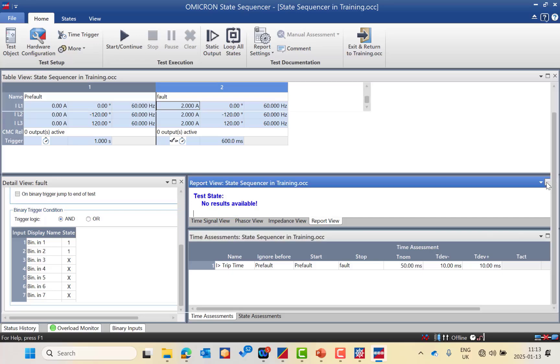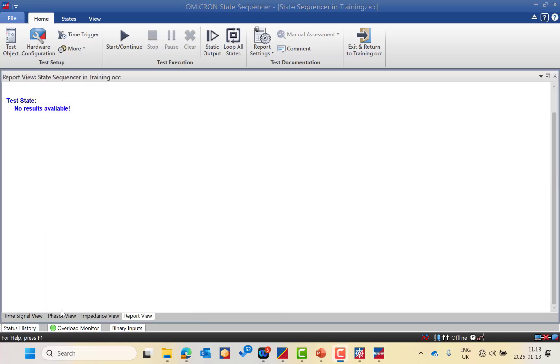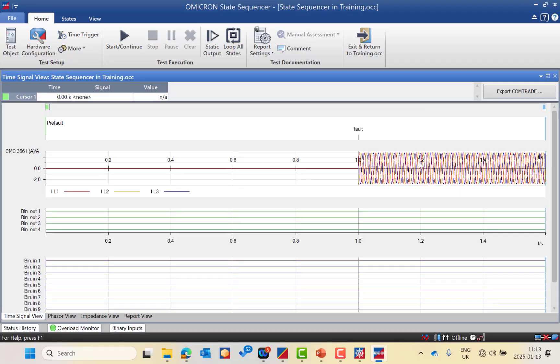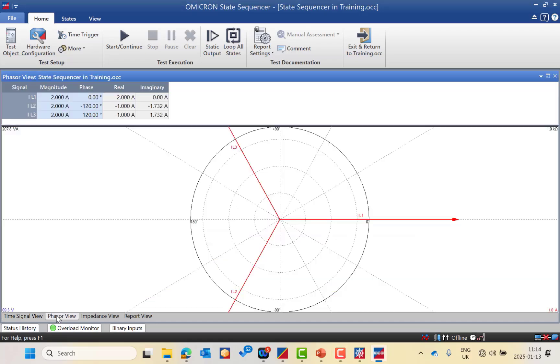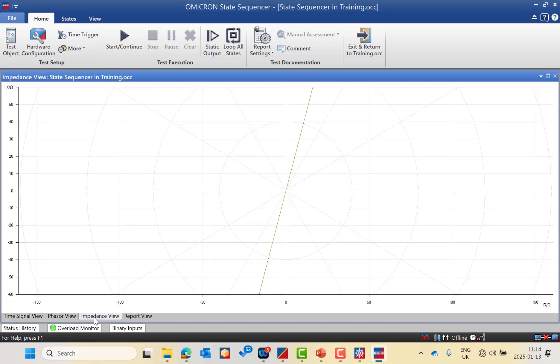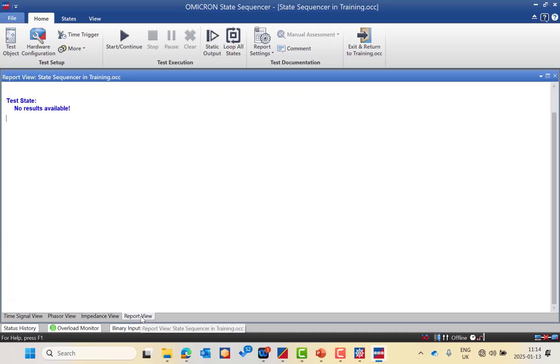We have the time signal view, which shows analog voltage and analog current, binary output status, and binary input status in blue — indicating after the fault, after 500 milliseconds, binary input 1 goes high. We also have the phasor view for injected current and voltage, the impedance view for impedance plane or quadrature zone reach display, and the report view.